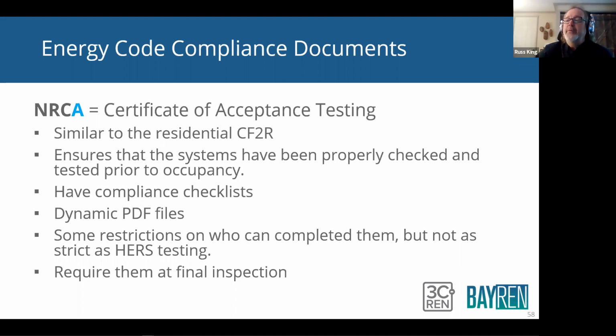And there are forms, NRCA forms. If you're used to the residential side, it's similar to a CF2R, okay? It ensures that the system has been properly checked and tested prior to occupancy. So if you look at an NRCA form for, say, outside ventilation air, it'll have a very precise checklist of things that need to be done. Turn the system on, turn it to cooling, measure the airflow, measure the outside airflow. Does it meet this percent? Does this number exceed this number over here? If yes, check this box. It's very precise, step-by-step instructions for how to test a certain feature in a building.